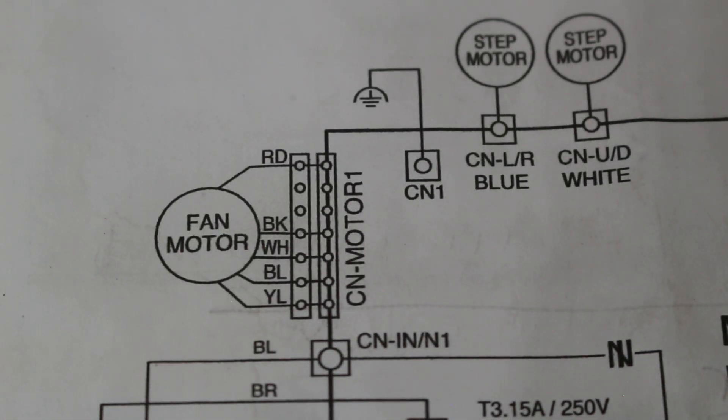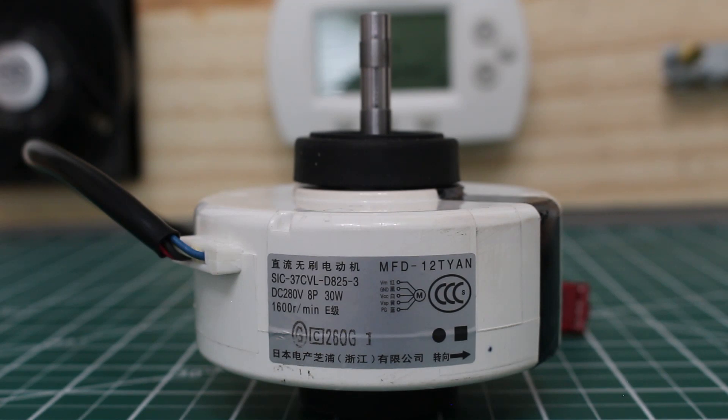It is definitely safer to check when the power is off, checking resistance. If the motor is getting proper voltage and it's not spinning, most likely you have a bad motor. Or you can also check with the power off by checking those resistance readings. Personally, I like checking with the voltage. Just remember you're dealing with a high voltage and it's dangerous, so it would be up to you. It's getting voltage, not spinning, bad fan motor. If it's not getting voltage, well, you need to look into why it's not giving out the voltage. And pretty much, that's the way you check it between voltage and resistance. And more or less, you should have an understanding on how to do that.